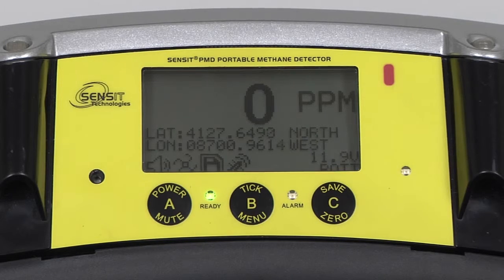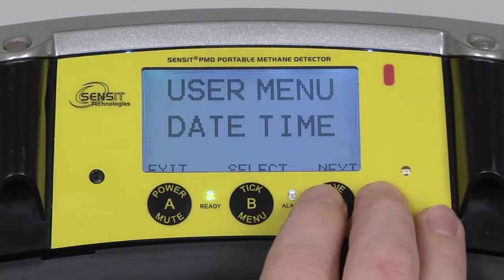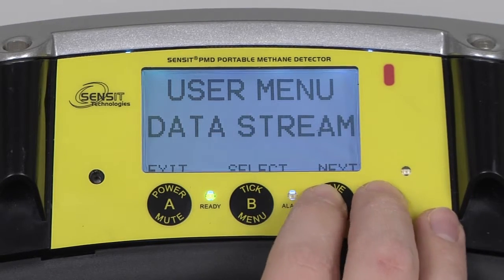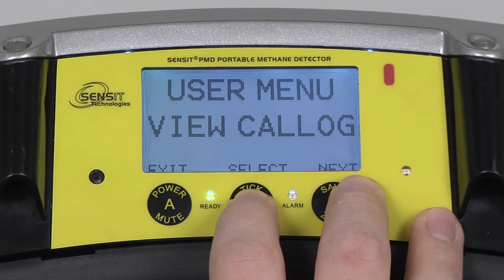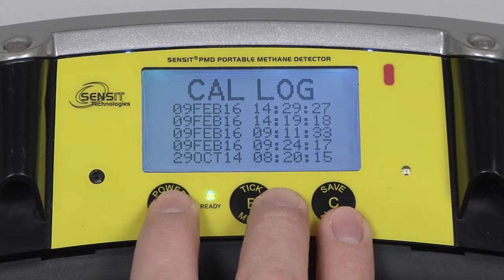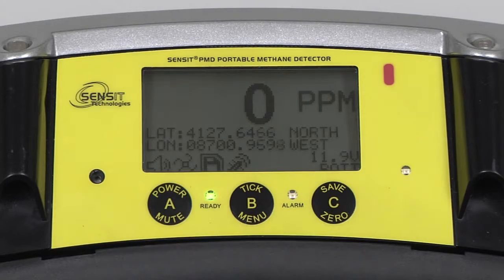To verify the calibration date of the PMD, enter into the user menu by pressing and holding the B button, and scrolling by pressing and releasing the C button until View CalLog appears. Enter into this by pressing and releasing the B button, and up to five previous calibration dates will be displayed, with the topmost being the most recent. To exit, press and release the A button until we arrive back at the working display.